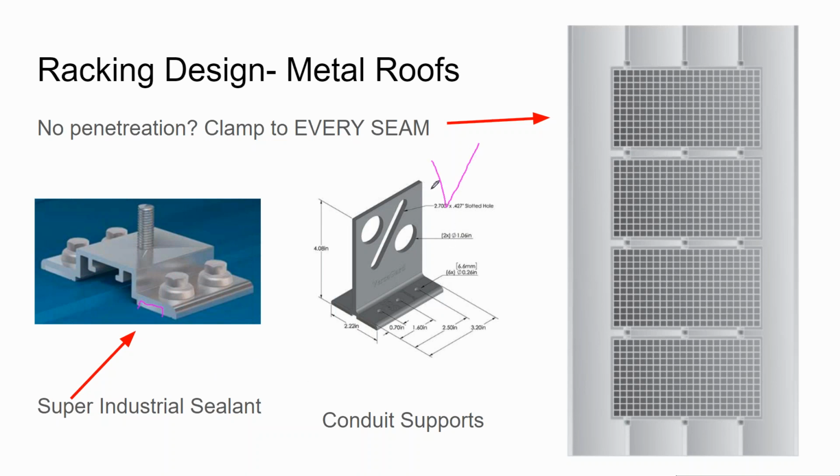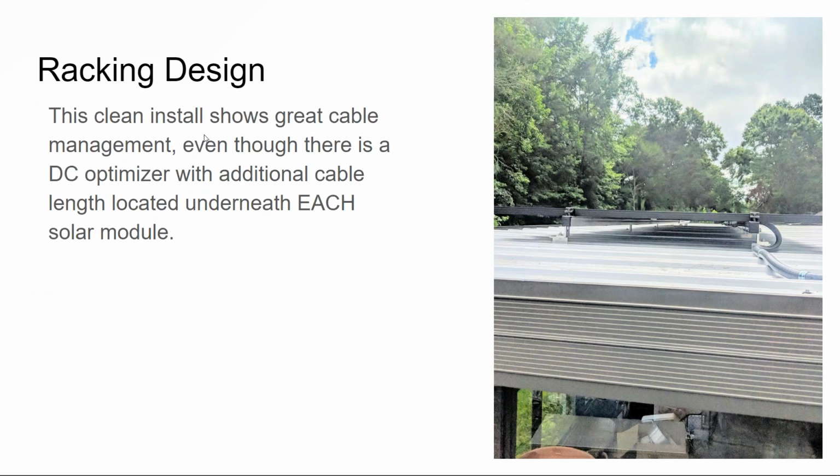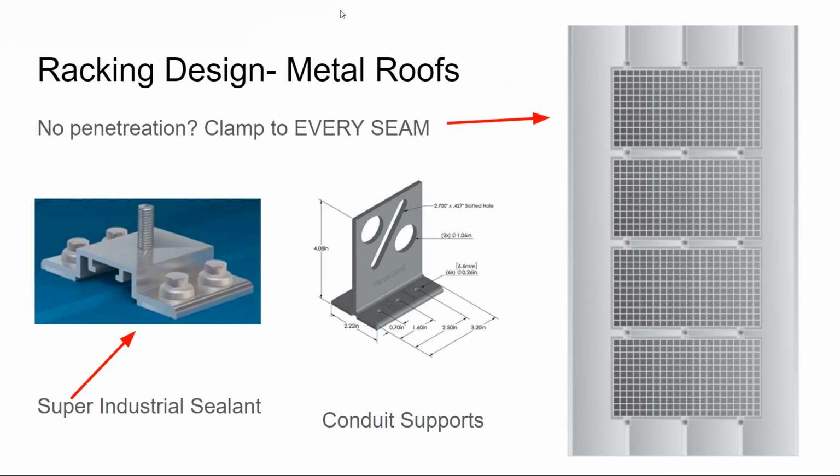And I even found conduit supports that have the same kind of attachment. This is the S5 manufacturer. So these conduit supports were kind of neat. The only thing I don't like about this picture is kind of how messy this flex conduit looks. Get that up off of the rooftop with these conduit supports.